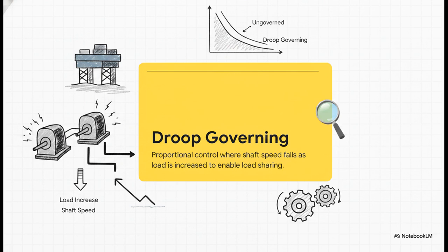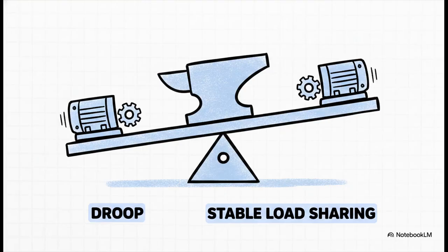It basically tells the engine, hey, as the electrical load gets heavier, just allow your mechanical speed to drop slightly. The key metric you need to know here is that a standard 4 to 5% drop in speed is expected when a 100% load is applied. For example, if your system runs at 50 Hz at no load, slapping a full electrical load on it will cause the frequency to naturally droop down to roughly 48 Hz. This predictable sluggishness is exactly what lets two or more massive generators operate in parallel safely. They share the power demand without constantly fighting each other for control and tripping the whole platform offline.